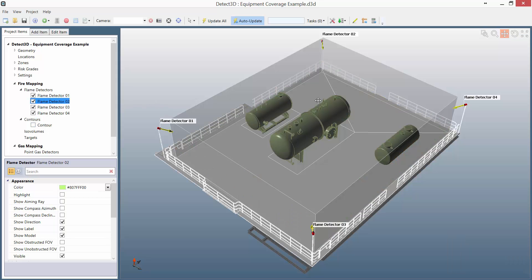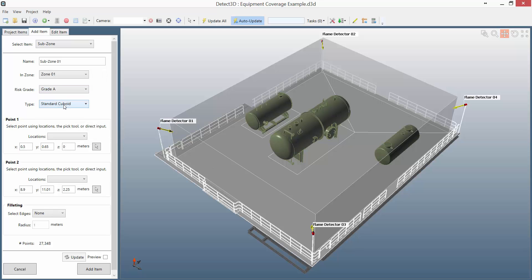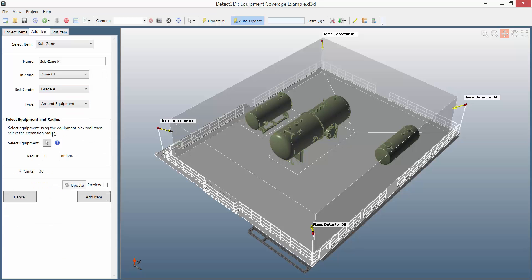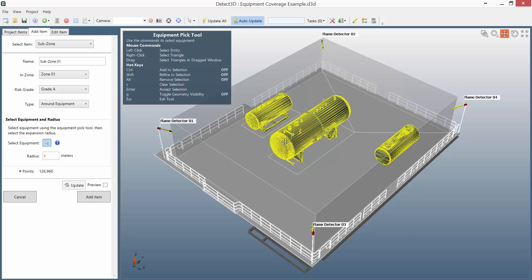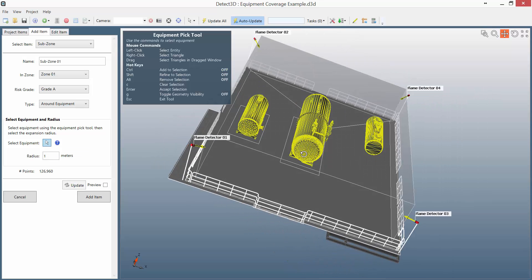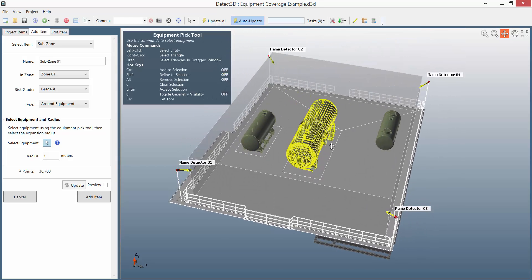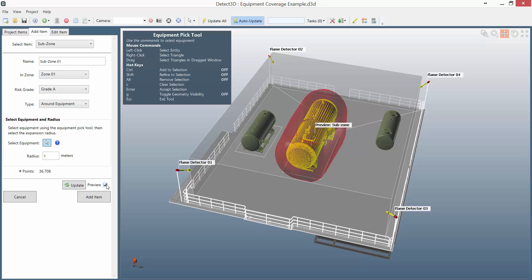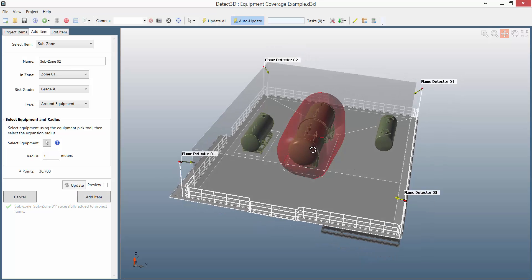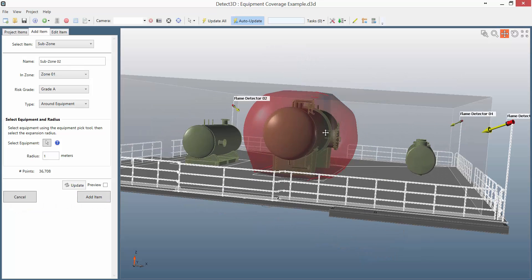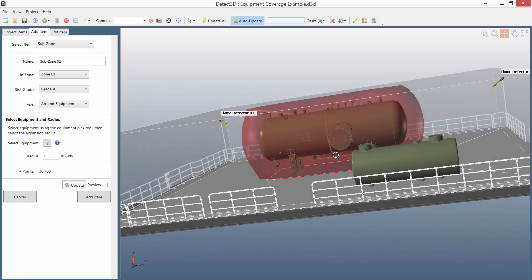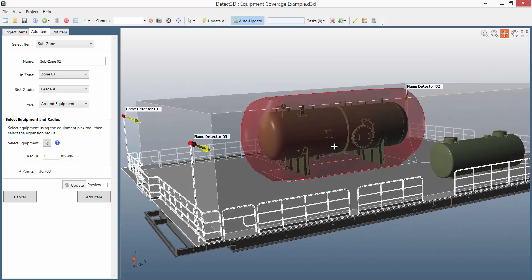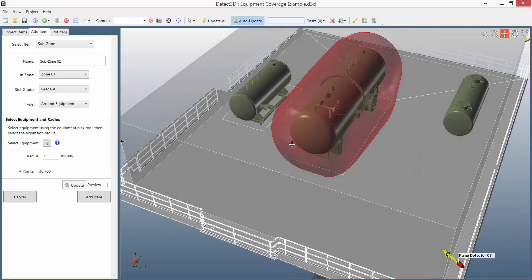You can see that I have these three vessels in the example, and around these vessels, I might be interested in a smaller fire of, say, 1kW. In that case, what I can do is set up a subzone around the equipment that I'm interested in using the new equipment pick tool. Using the pick tool, I can select the vessels, and then refine my selection to only include the middle vessel. Once I'm happy with it, I can preview the new subzone and add it to the project. What has happened here is that the software has constructed a subzone exactly 1m around the middle vessel, mirroring its irregular shape, but limited by the extent of the zone in which it resides.